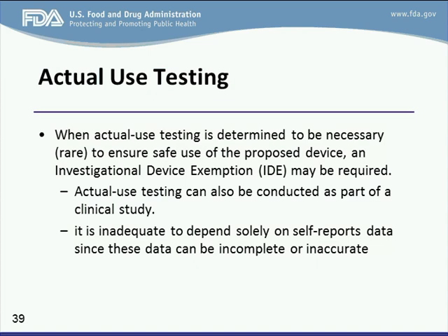Most likely for that, an IDE study might be required. And you can consider conducting the actual use human factors testing as a part of the clinical study. And for those scenarios, we highly recommend you submit a pre-submission to have a discussion with the agency before you launch your human factors testing.